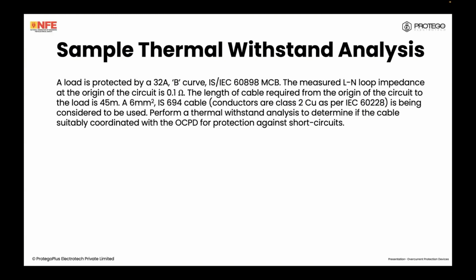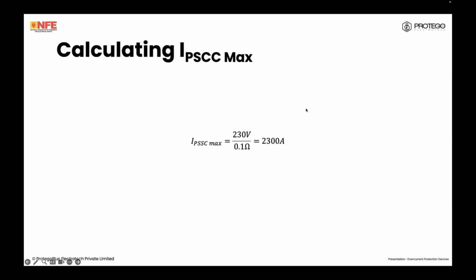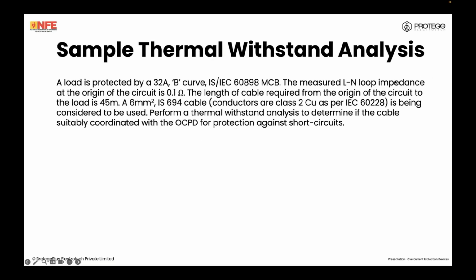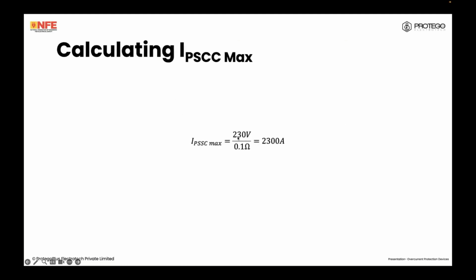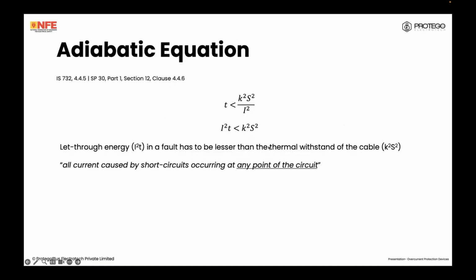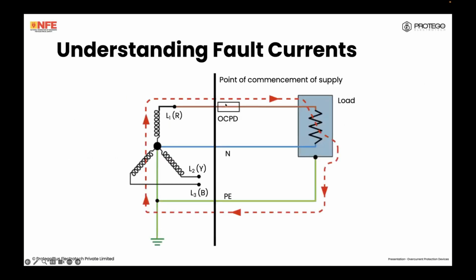Perform a thermal withstand analysis to determine if the cable is suitably coordinated with the OCPD for protection against short circuit. Somebody asked us, "Hi, how is the multiple circuit breaker selection with respect to short circuit in the same circuit?" This is how you do it. I'm telling you that the line to neutral loop impedance is 0.1 ohms at the origin. So IPSCC max is going to be 230 volts divided by 0.1 ohms, 2300 amps, which is the fault current here.